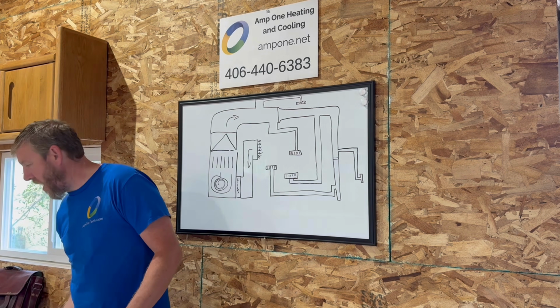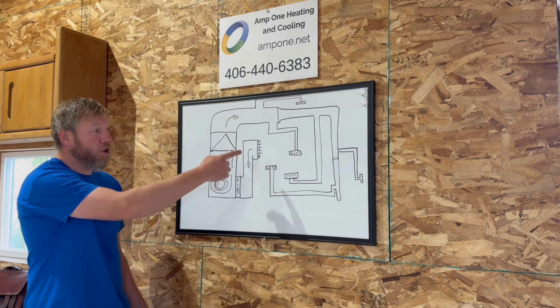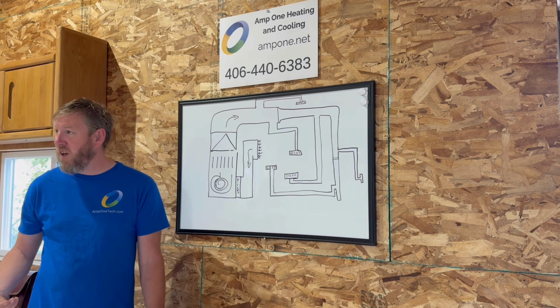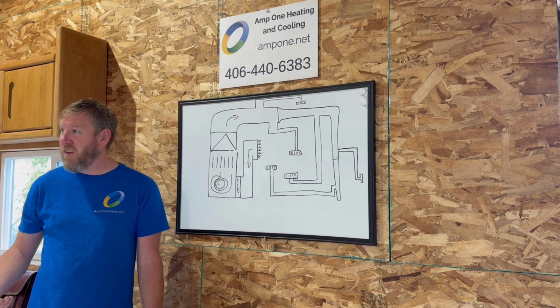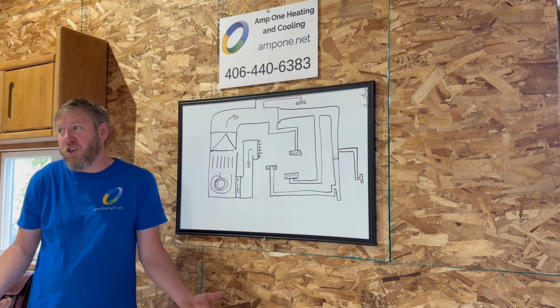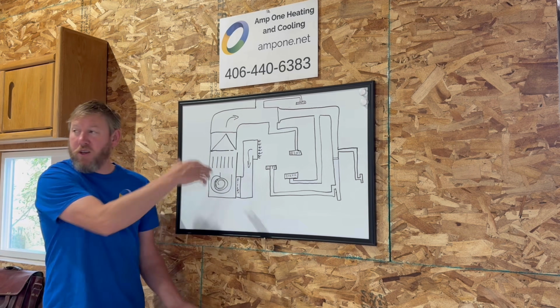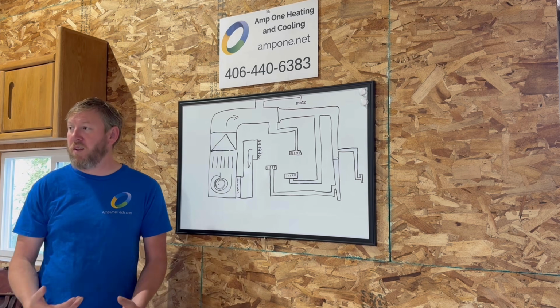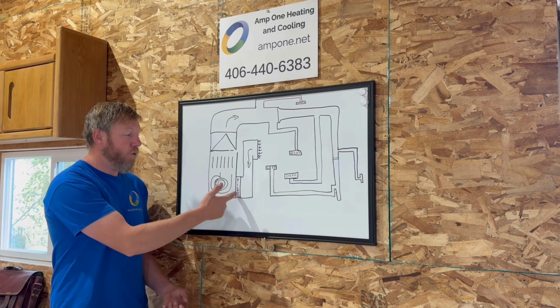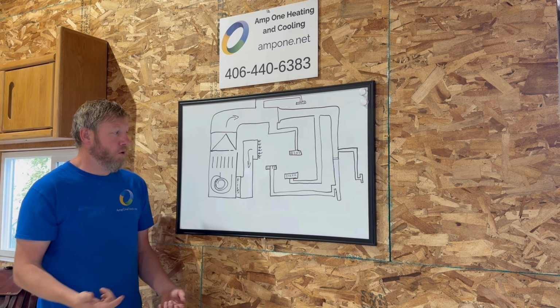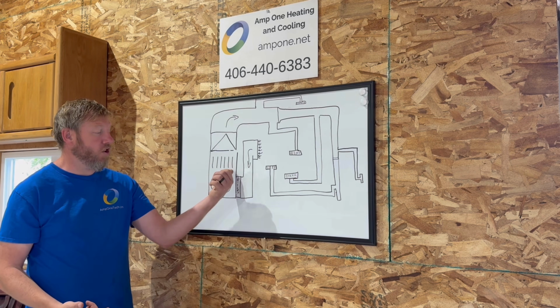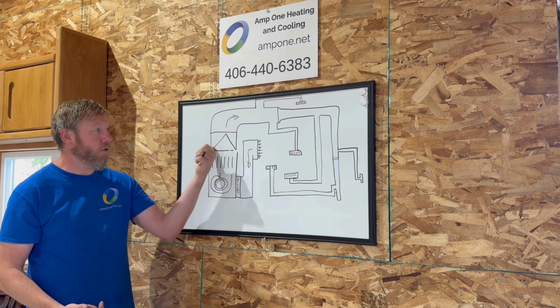Airflow, that's why you have to have return air. Return air is huge. You've got to get enough back to the system. That's why I always check my return air first. Make sure that everything's, what is it breathing? What's it taking into its system? What's going on with the filter? How's the fan motor running? What's the secondary heat exchanger look like? Is there a problem with the A-frame coil?